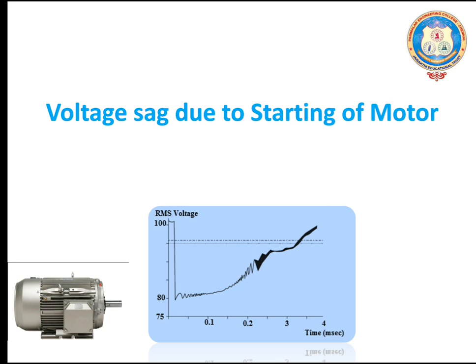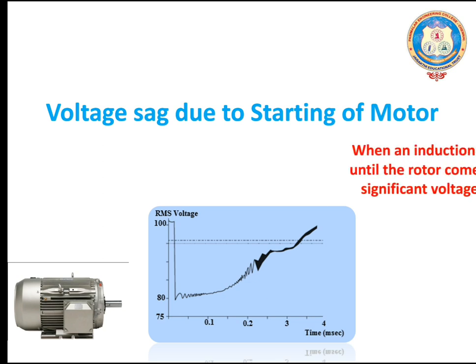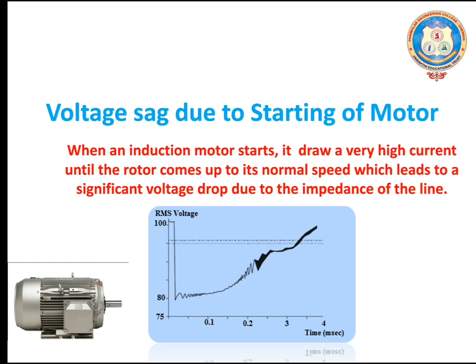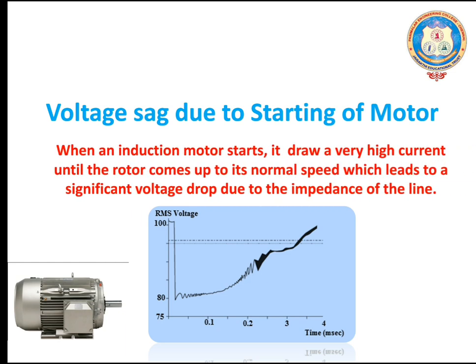How does Voltage Sag occur due to starting of a motor? When an induction motor starts, it draws a very high current until the rotor comes up to its normal speed, which will lead to a significant voltage drop due to the impedance in the line.